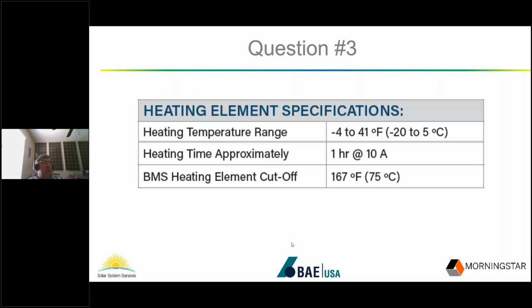So this is an example of one that actually uses the solar array, and it says you need 1 hour for a 100 amp hour battery, by the way. Most of these are for 100 amp hour, 12 volt batteries, standard group 27 or group 30. So it's using 1 hour at 10 amps to heat the battery up before you can start charging.